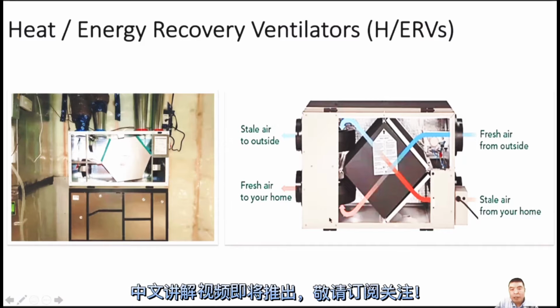In fact, from the outside we cannot see any difference. HRV and ERV look the same, and everything inside is almost the same. We can open the door and see inside. This is a heat exchanger, and these two are the filters. There is a blower motor here and another one here, so there are two motors. The two fans are one for exhaust and one for intake.